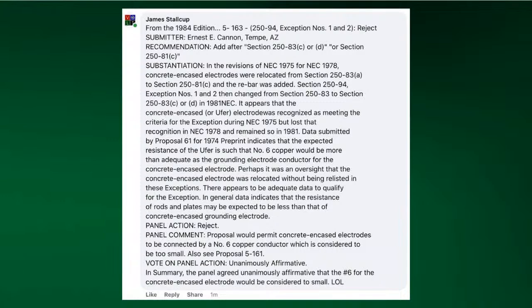Yep. Now, I didn't make any of this up. This is exactly, you can go back and look at 5-163 and you'll see the panel specifically stated. And if you notice, the language didn't change. So if the language didn't change, how am I allowed to go smaller than what is listed there for the ground rod or the concrete encased electrode when they're telling you here that it's considered too small?